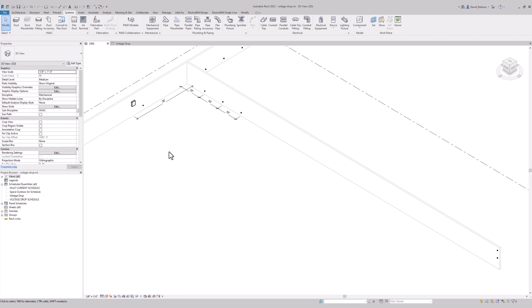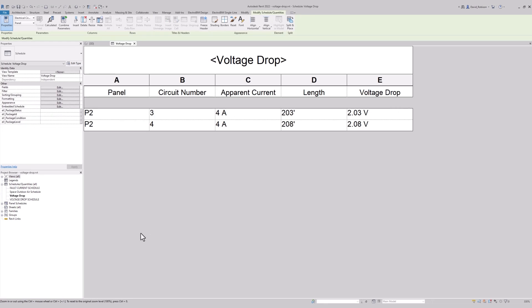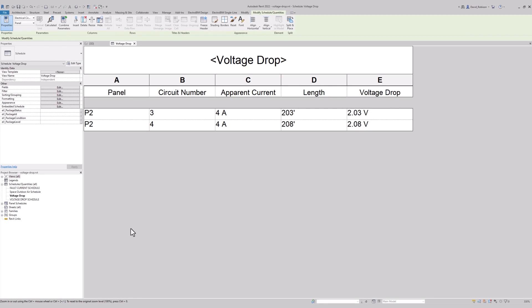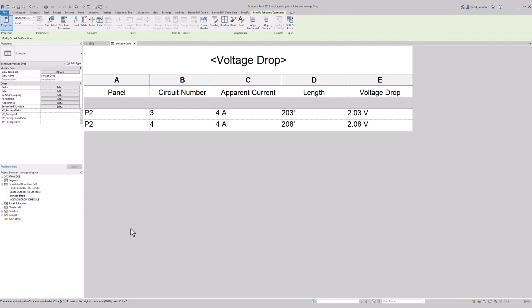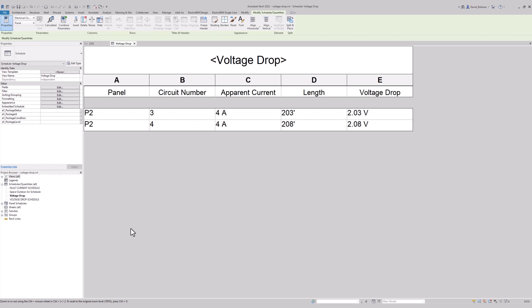So you have a voltage drop that's going to be far higher than it would actually be in real life. You really want the voltage drop on these two circuits to be different because they are actually modeled differently. If we go look at how those voltage drops are calculated in Revit, you can see they have essentially the same voltage drop. The interplay between load and length in Revit isn't great, but it's probably something you could work around if you were trying to use Revit for your voltage drop.